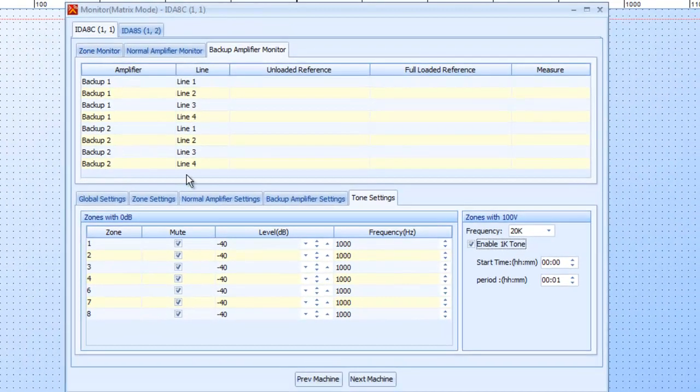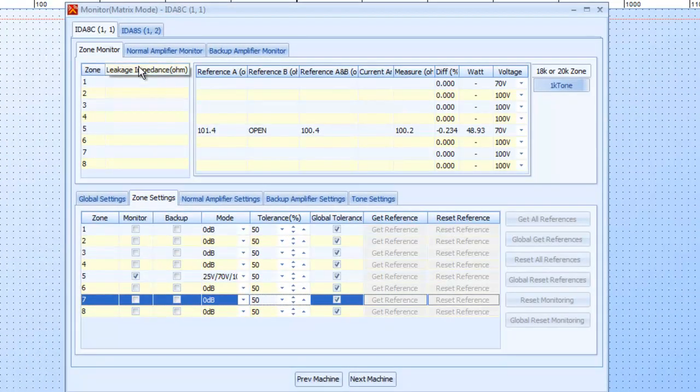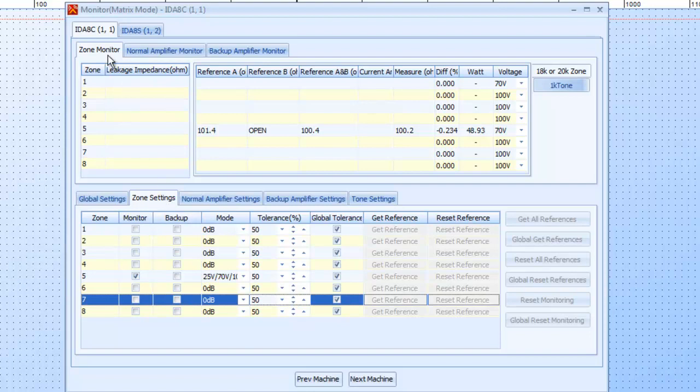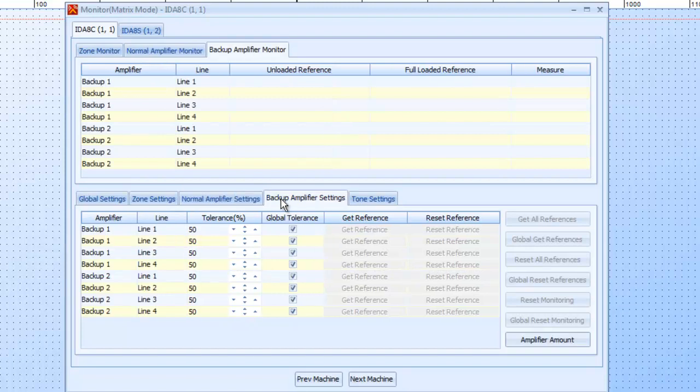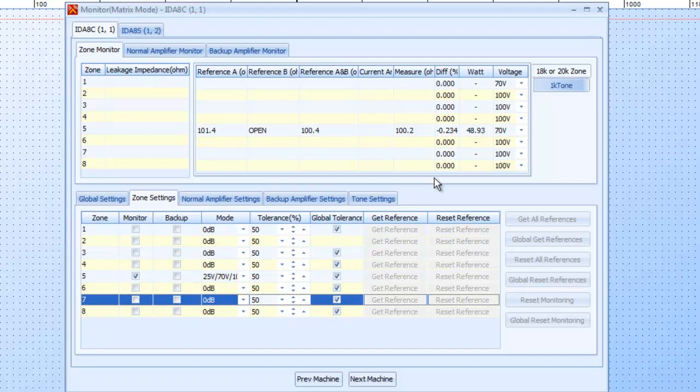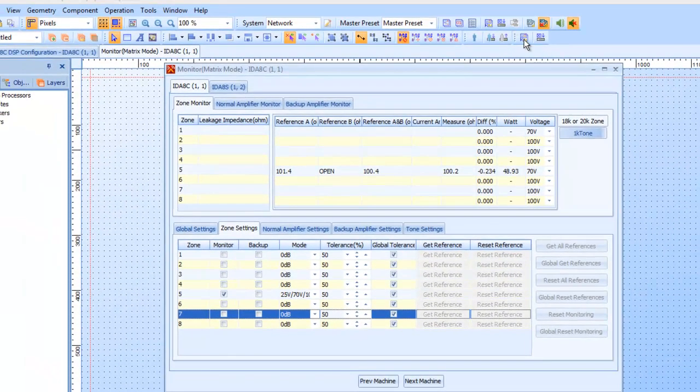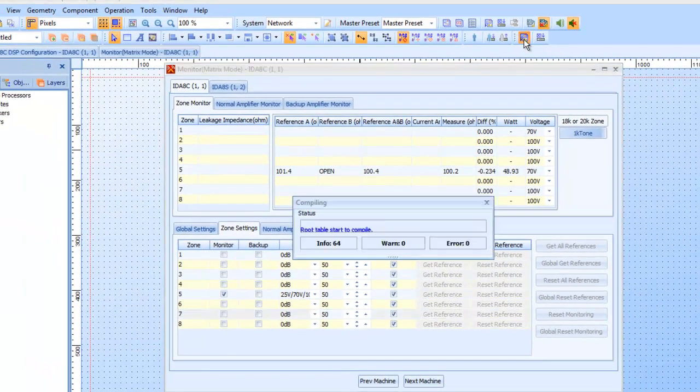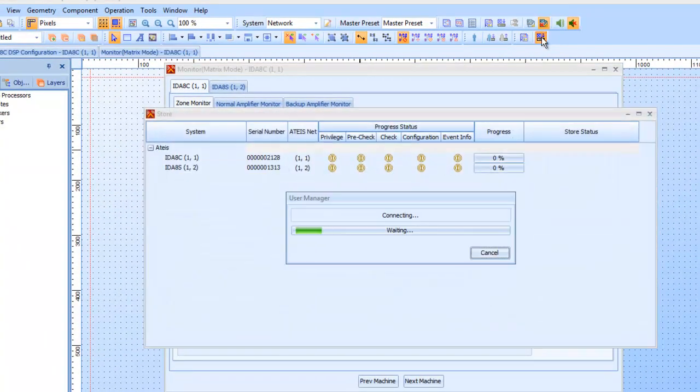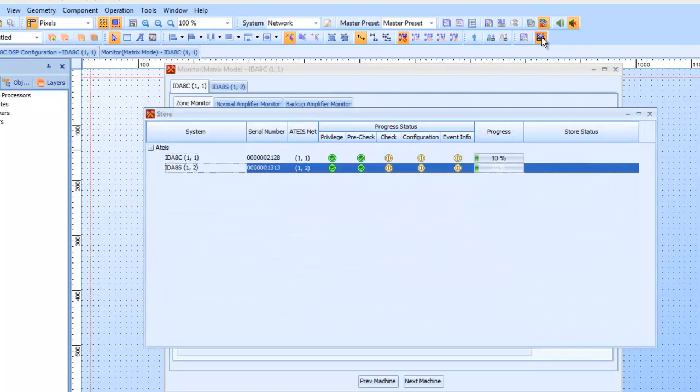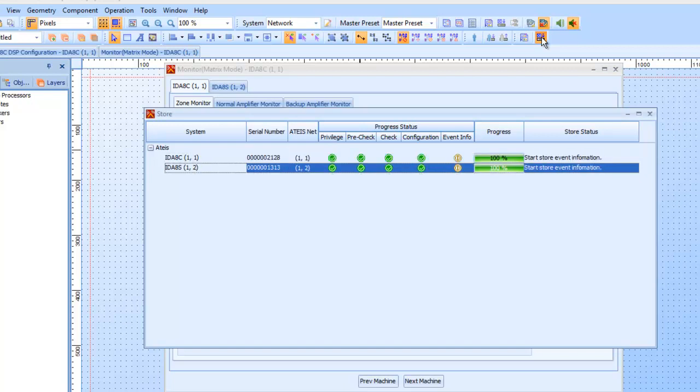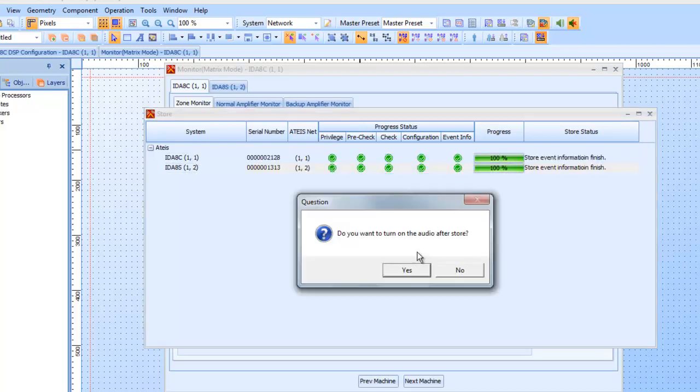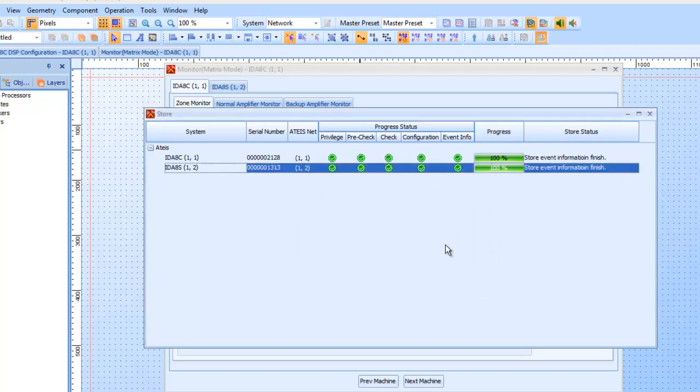We set up all those. So let's go back up here. We can go to our zone settings here and it automatically goes up here at the top to your zone monitors. If I switch the amplifiers normal back up, it switches up here at the top as well. Once I've done all these global settings, let's go up here and compile. There we go. And we will store because remember, you cannot make any of these settings while you're online. Those settings or configuration settings must be done when you're offline in program mode. All right. We'll turn on the audio and we'll go online.